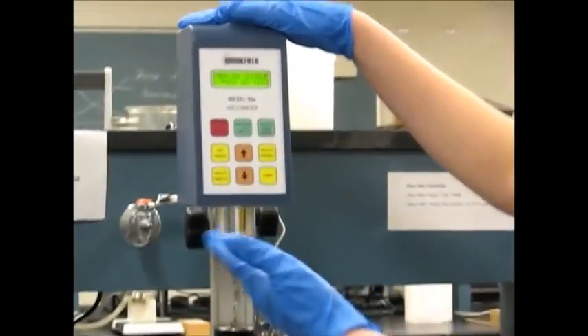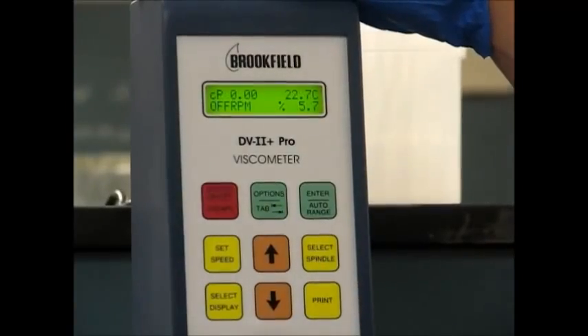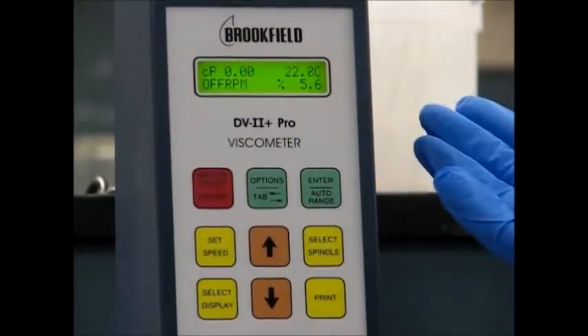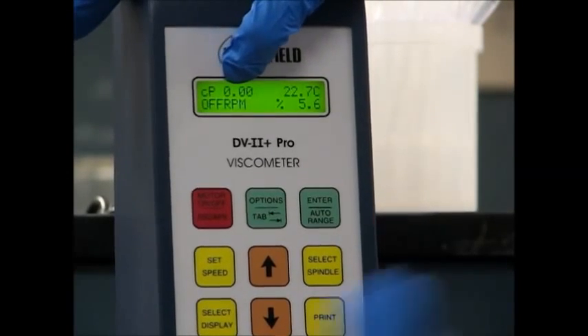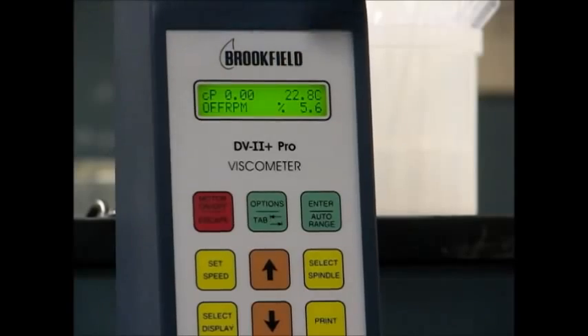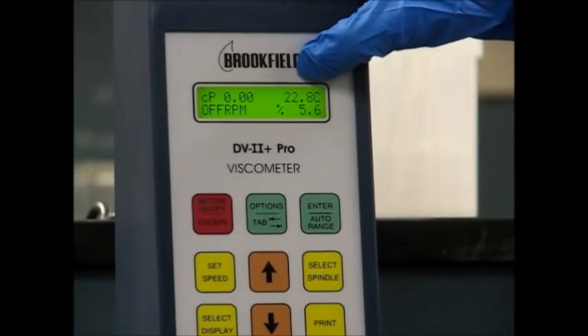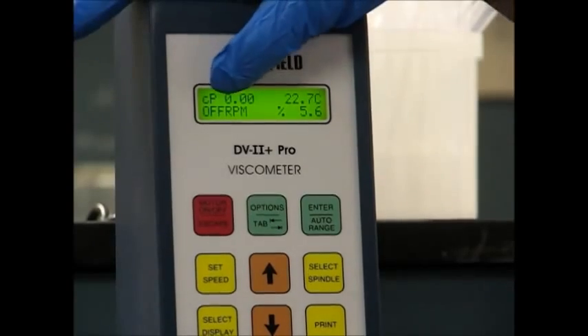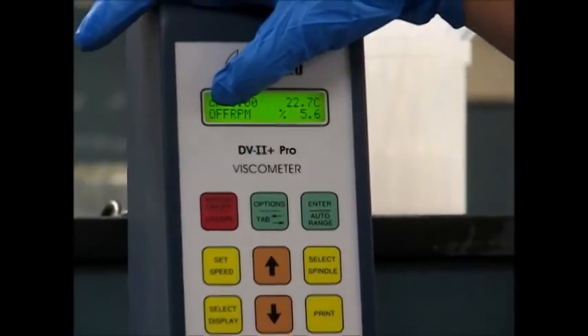Since we've replaced the spindle, we're going to keep following the directions. There's four different things that you can see from this. You can see the viscosity, once it will measure once it's turned on. You can see the temperature of the fluid. You can see the percent torque, and you can see the rpms. Right now, it's off.